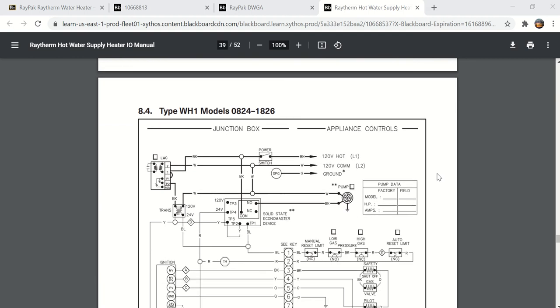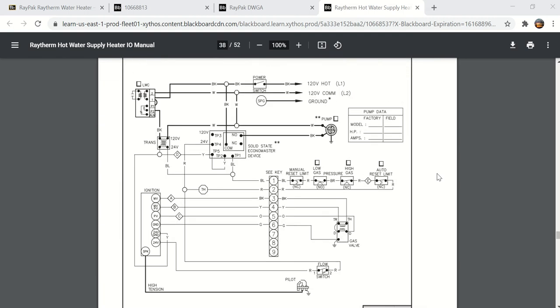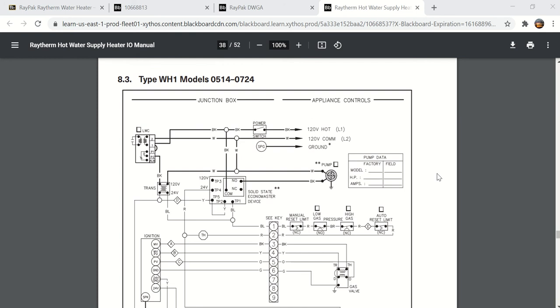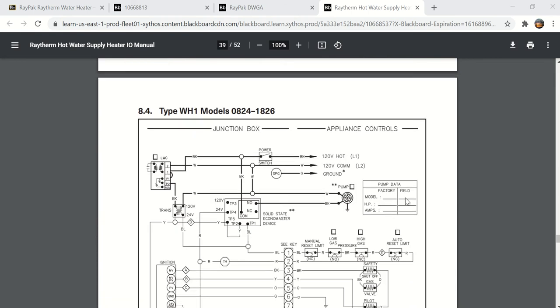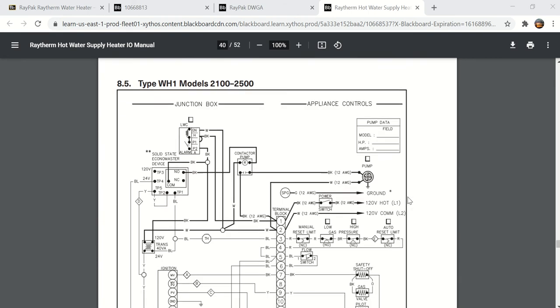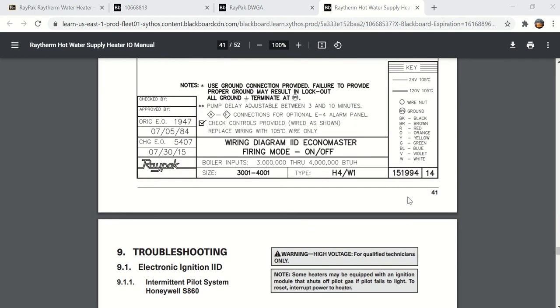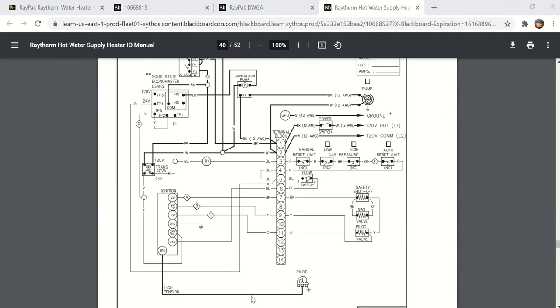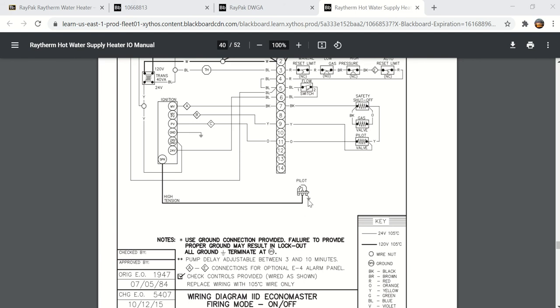The closest one to it is probably this one here. This one would be fairly similar to the one we just did, and again, here's the boxes. Well, I guess that one has high and low gas pressure, so maybe that's not the closest one. But you'll see on all of these drawings, from the spark terminal on the ignition control, it says it's a high tension wire. It should be a thick insulated, usually silicone type wire that goes to the ignition. And I think it's pretty important to see that they're showing this actually has to be grounded. And you'll see right here on the ignition control, it has a ground terminal, which also has to be grounded.